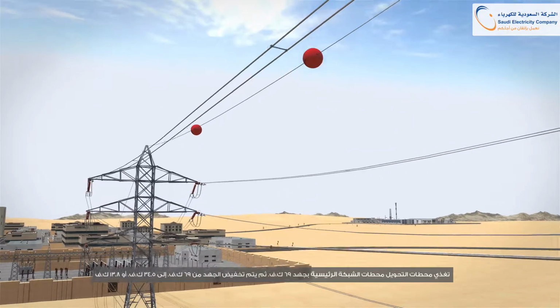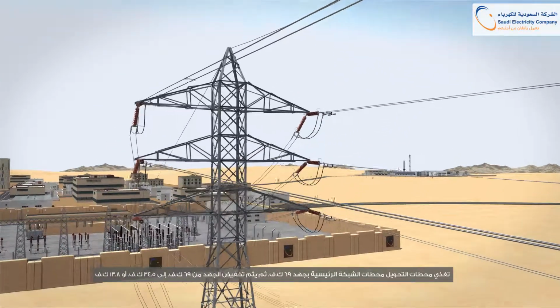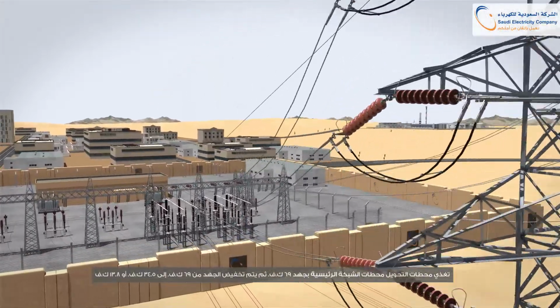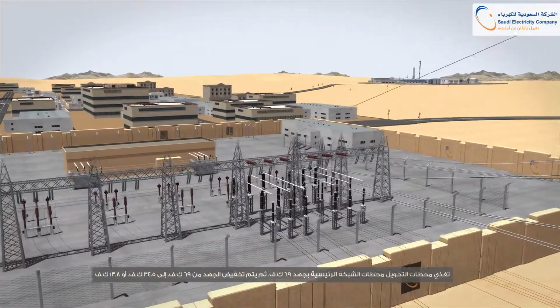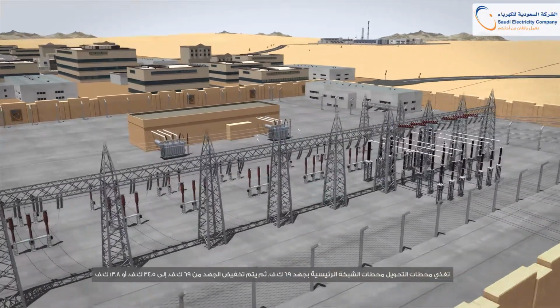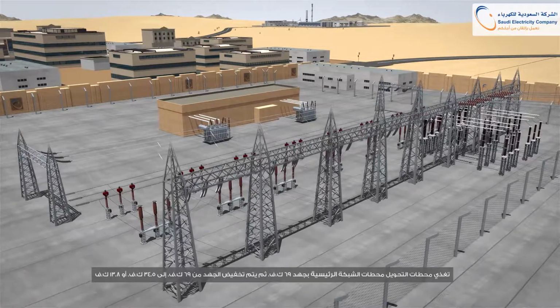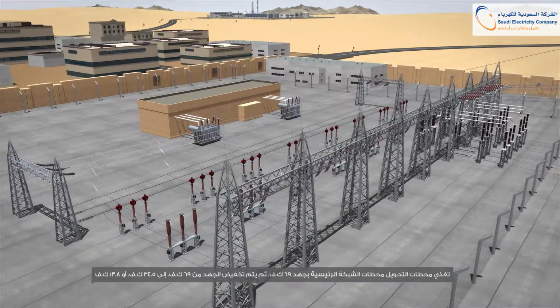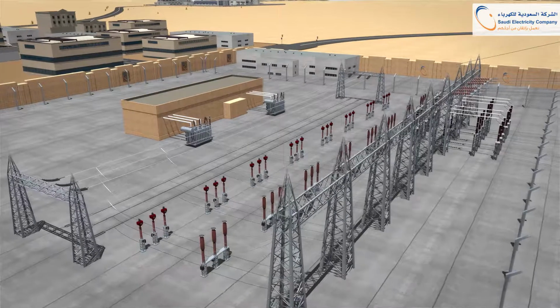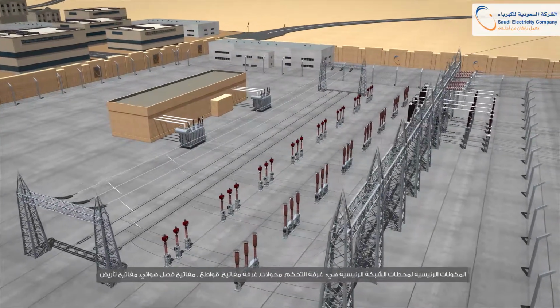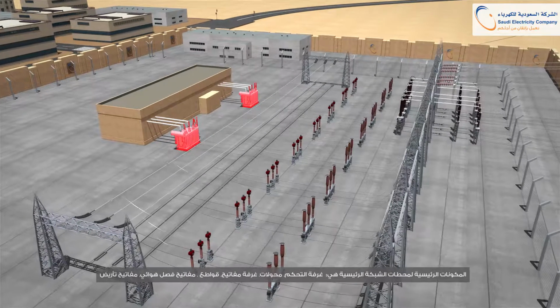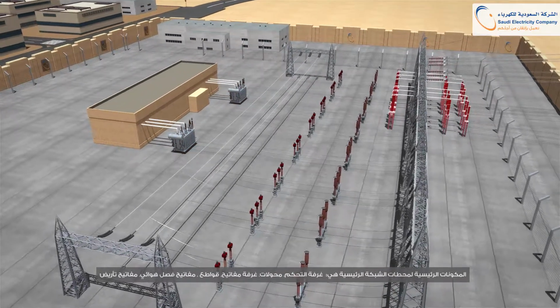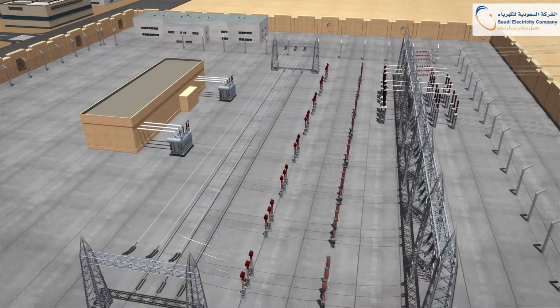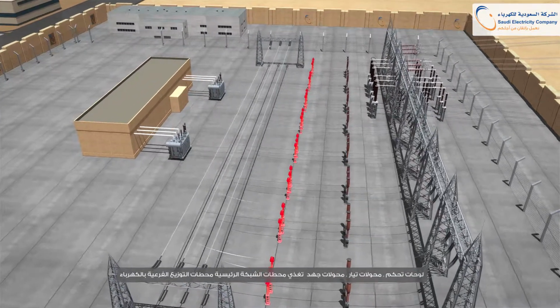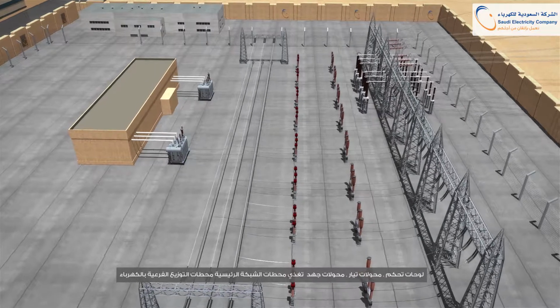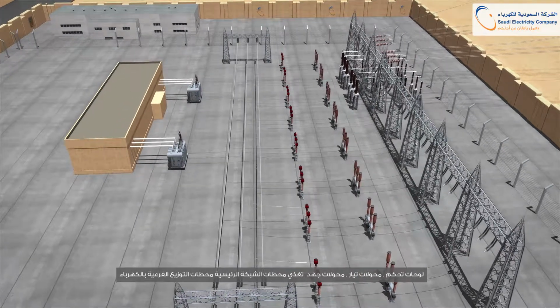The bulk supply point, 230 kV, feeds grid stations with 69 kV. Then the grid stations step down the voltage from 69 kV to 34.5 kV or 13.8 kV. The main components of the grid station are the control room, transformers, switchgear, circuit breakers, disconnect switches, earthing switches, control panels, current transformers, and voltage transformers. Those grid stations supply power to distribution substations.